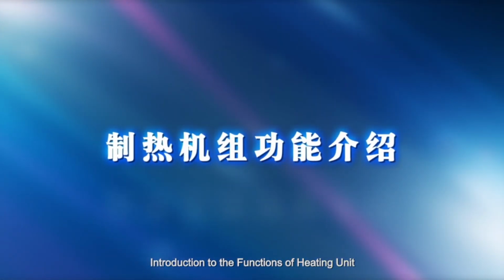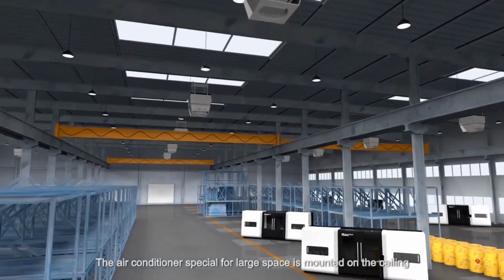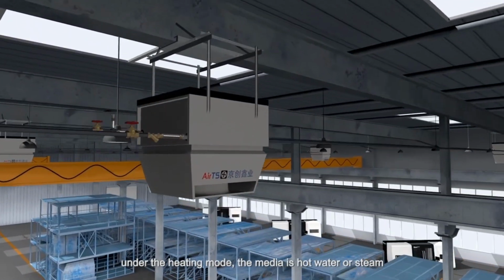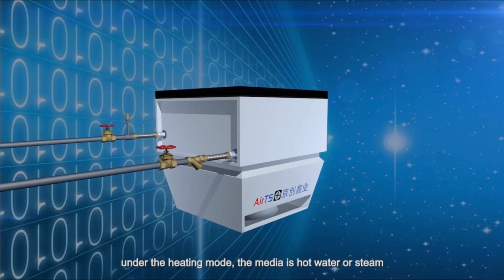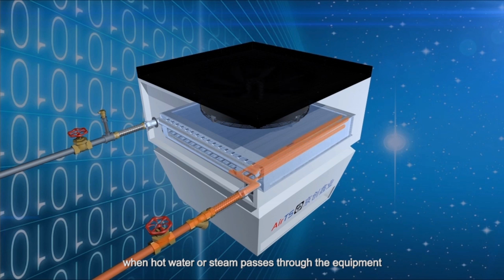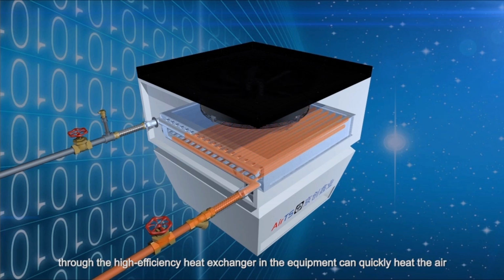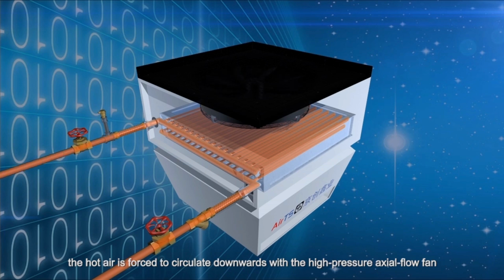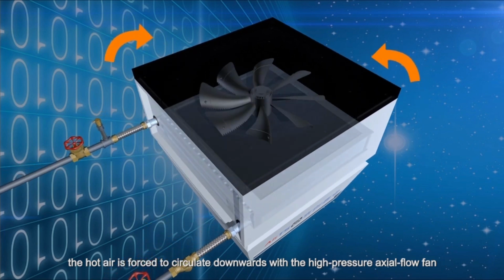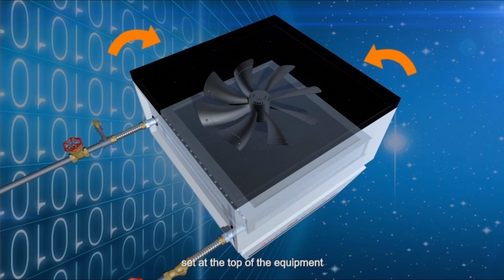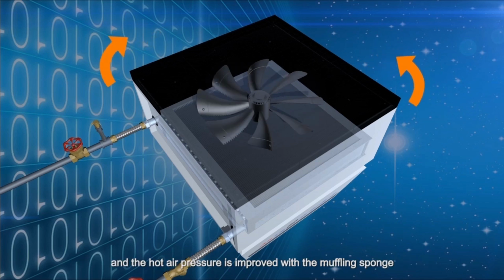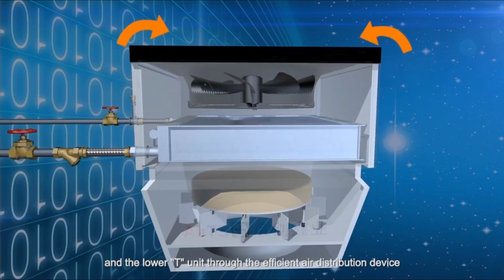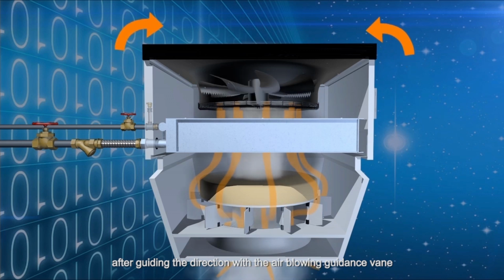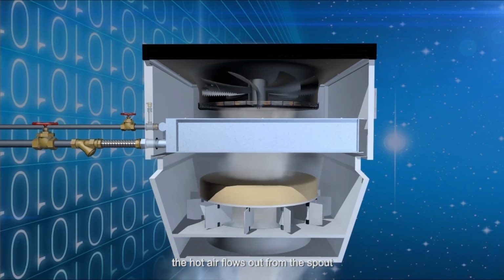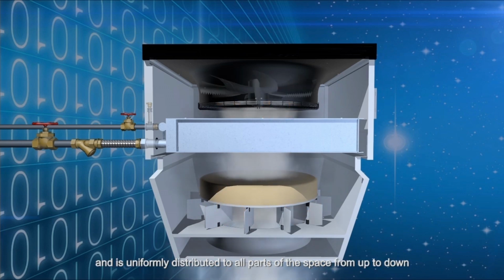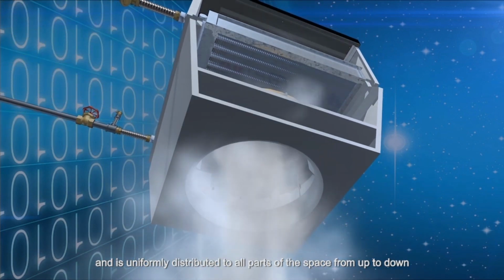Introduction to the functions of heating unit. The air conditioner special for large space is mounted on the ceiling. Under the heating mode, the media is hot water or steam. When hot water or steam passes through the equipment, through the high-efficiency heat exchanger in the equipment can quickly heat the air. The hot air is forced to circulate downwards with the high-pressure axial flow fan set at the top of the equipment, and the hot air pressure is improved with the muffling sponge and the lower T unit through the efficient air distribution device. After guiding the direction with the air-blowing guidance vane, the hot air flows out from the spout and is uniformly distributed to all parts of the space from up to down.